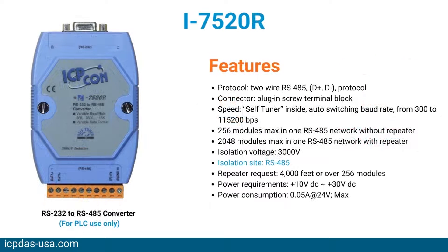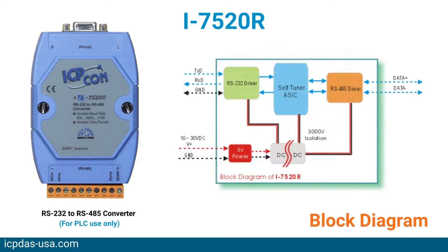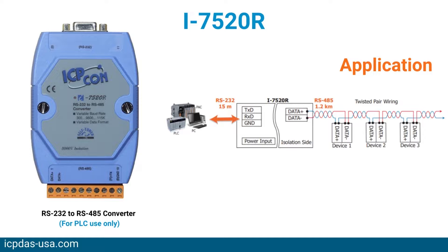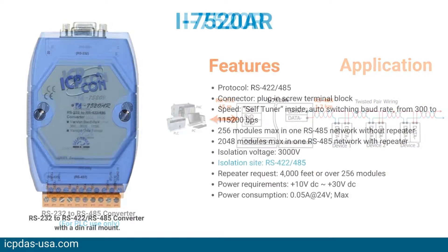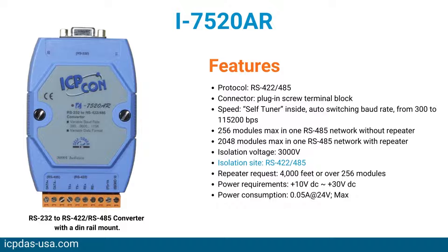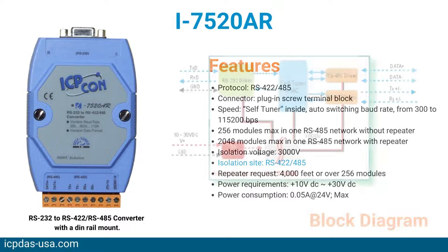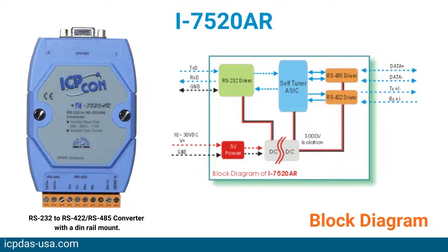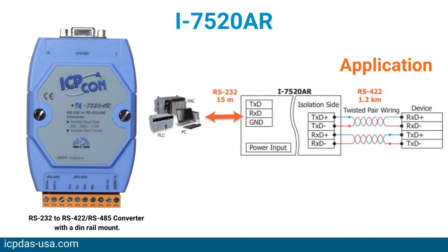The design of the isolation between the I-7520 and the I-7520R and AR is different. If the user wants to supply power from the PLC or PC, the I-7520R or AR should be used, otherwise isolation will be broken. You can click the link in the description to refer to the I-7000 bus converter manual for detailed information.